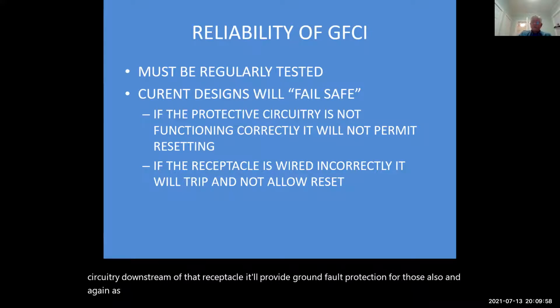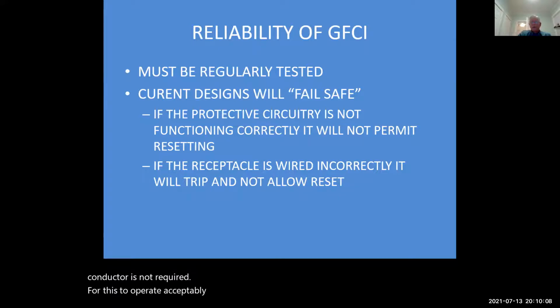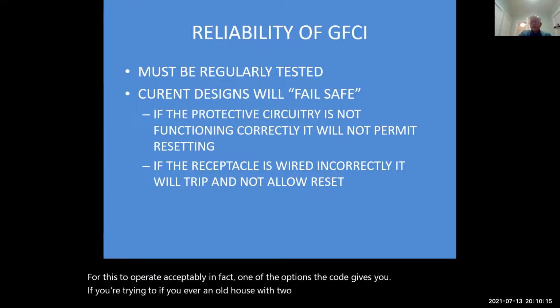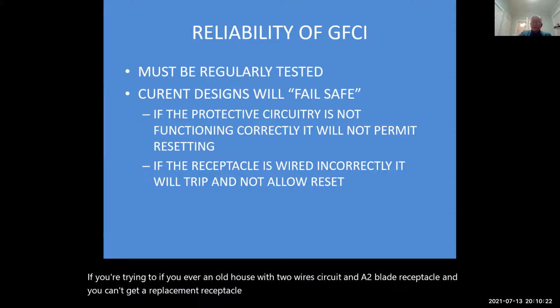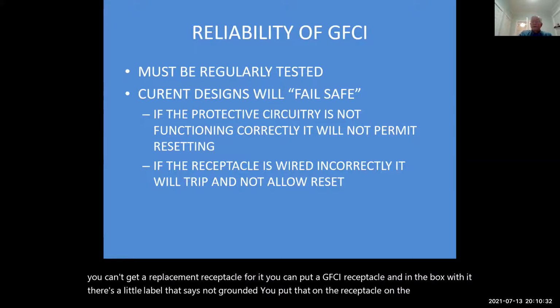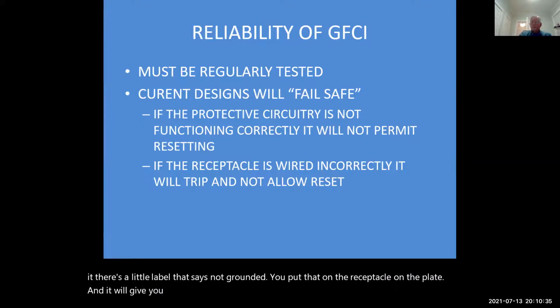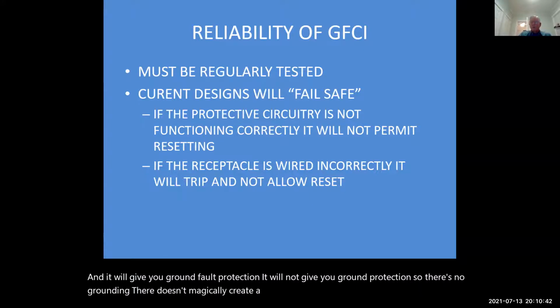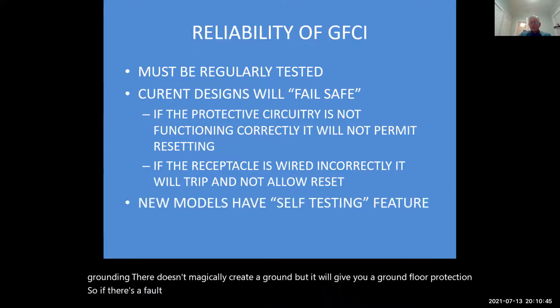And again, as I said, a grounding conductor, the equipment grounding conductor, is not required for this to operate acceptably. In fact, one of the options the code gives you, if you have an old house with a 2-wire circuit and a 2-blade receptacle, and you can't get a replacement receptacle for it, you can put a GFCI receptacle, and in the box with it, there's a little label that says "not grounded." You put that on the receptacle plate, and it will give you ground fault protection. It will not give you ground protection, so there's no grounding there. It doesn't magically create a ground, but it will give you ground fault protection. So if there's a fault, it'll trip out before you end up fried.